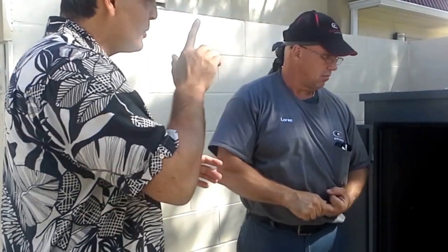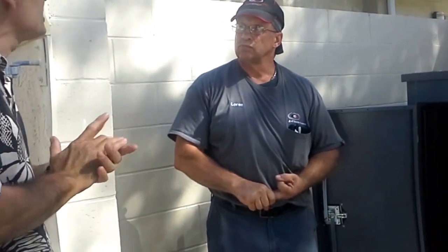That's a call that I would like you to make today, because I will program that ATS in order to run that in that amount of time. You want to run it weekly? For how long? Ten minutes? I said 20 minutes is minimum. Twenty minutes, okay. They're very efficient. We're doing it every two weeks, for 20 minutes. Okay.